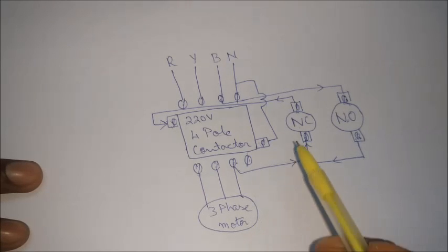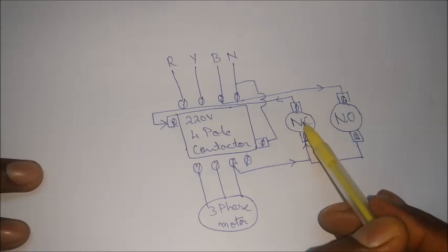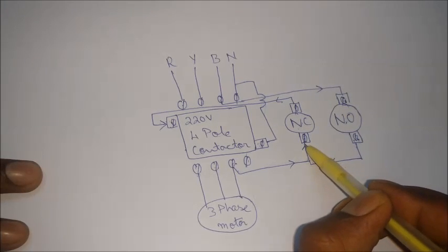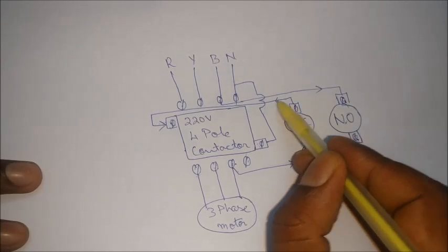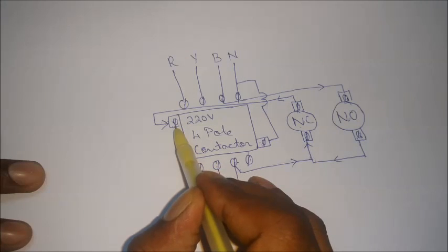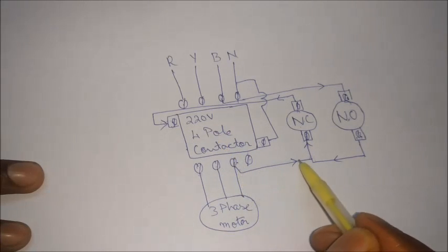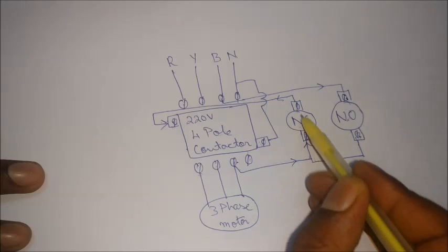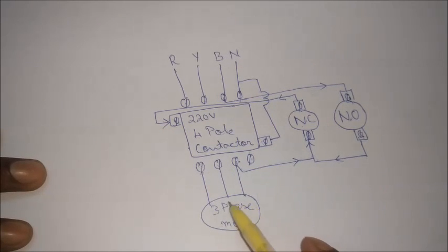Now when you decide to switch off the motor, you press the NC switch. Once you press the NC switch, current which has been coming from this will not come out of this when you press the NC switch. Hence the solenoid does not get current. The circuit breaks. So when the circuit inside this breaks, the current which was coming out of this point also breaks. So the circuit is totally broken and the motor will come to a halt.